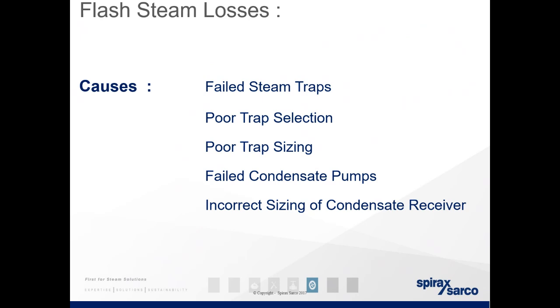Poor trap selection. If you're using a thermodynamic trap instead of a float trap where you're at the end of process, it could be that it's not clearing enough condensate, so that it's allowing condensate to build up, which is affecting the rest of the system. So you're transferring less heat to your process. You're having a buildup of water hammer, all those kind of things. Poor trap sizing. Again, if it's not large enough to cope with the load that is required, you will see more condensate in your steam system. And failed condensate pumps.